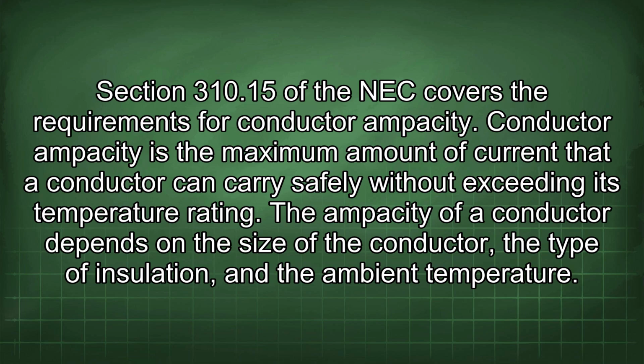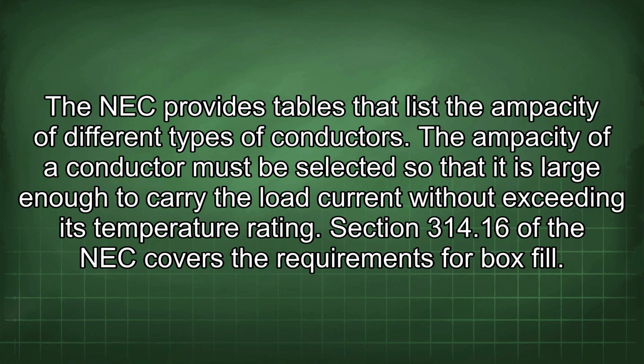Conductor ampacity is the maximum amount of current that a conductor can carry safely without exceeding its temperature rating. The ampacity of a conductor depends on the size of the conductor, the type of insulation, and the ambient temperature. The NEC provides tables that list the ampacity of different types of conductors. The ampacity of a conductor must be selected so that it is large enough to carry the load current without exceeding its temperature rating. Section 314.16 of the NEC covers the requirements for box fill.